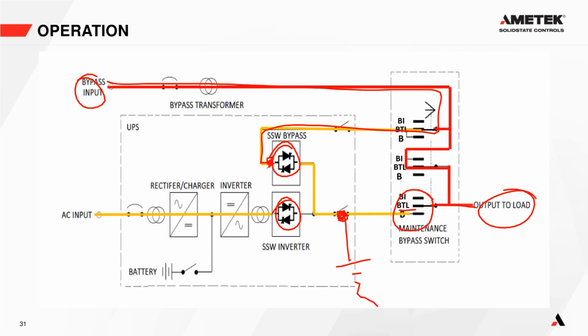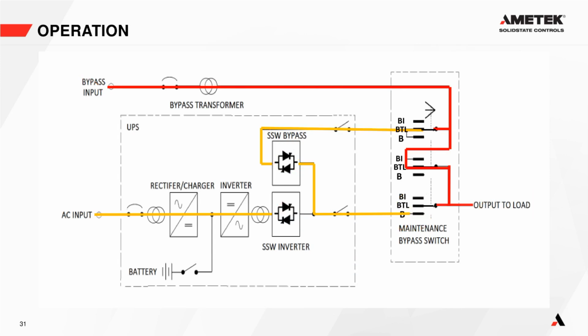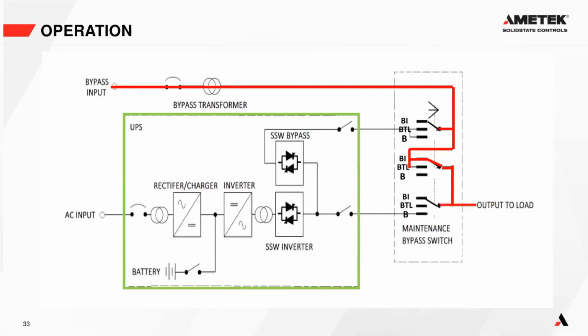And load the UPS up to 100% load if we really wanted to. What basically the bypass to load position allows us to test the UPS before going back to the normal position after we've had some intrusive maintenance. So very good question, but that's why we have the bypass to load position. It allows us to do testing of the UPS.